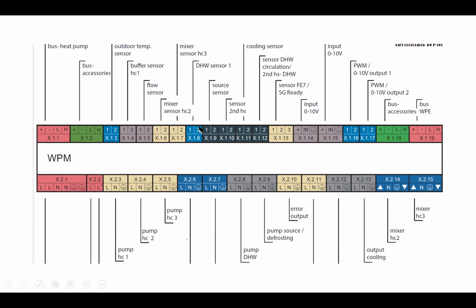So quite often, people will have thermostats and want us to control the manifold, or control manifolds. So what we say is, okay perfect, you control the pumps, we'll control the temperature. We'll put our sensors into heating circuit 2 and heating circuit 3, and we can control the mixers, so the mixer sits in position with the buffer tank at temp ready to go, and you just turn on the pump when you want water going to that particular circuit.